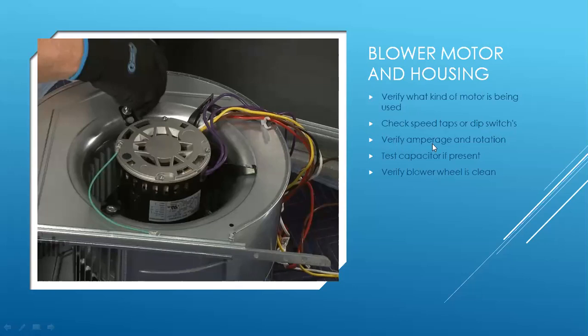A big one is verify amperage. It'll tell you on the data plate of your motor what your amperage should be, and then verify your rotation. I've come across a few motors in my time where guys didn't check the rotation, so it's actually going the opposite way. Sometimes you can hear it by sound; it just sounds wrong. But always check your voltage, amperage, and rotation. Same thing with the dual capacitor on the outside. If you've got a blower motor with a capacitor, you also want to test that capacitor as well.